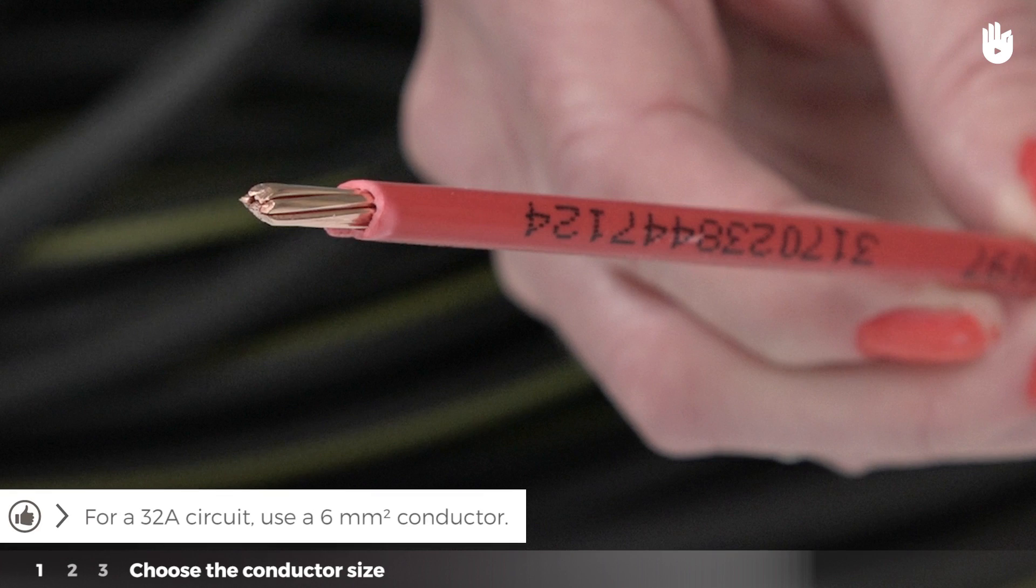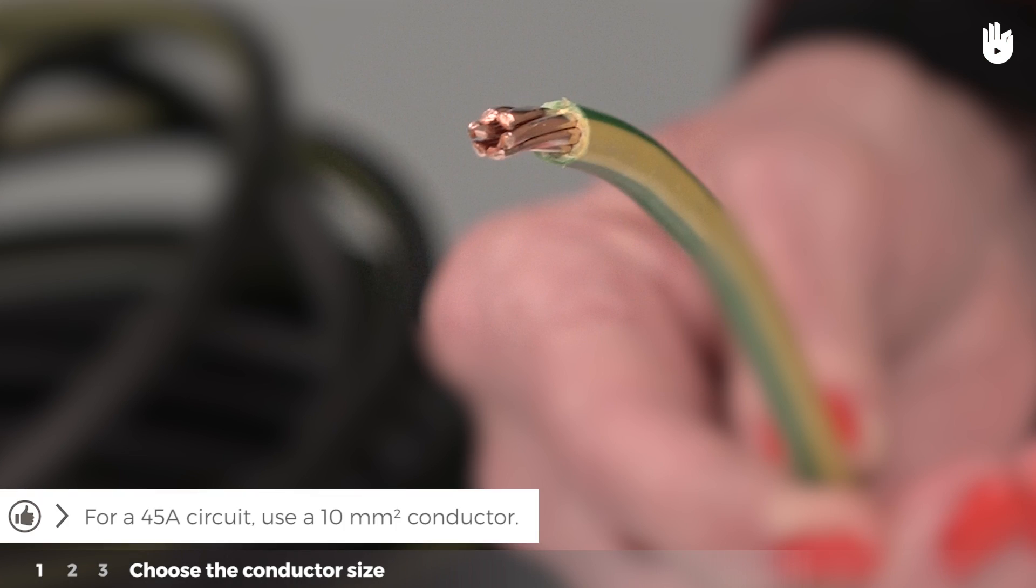For 32 amperes, a 6 mm conductor. Lastly, for 45 amperes, a conductor with a diameter of 10 mm squared.